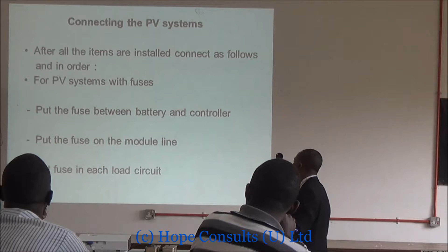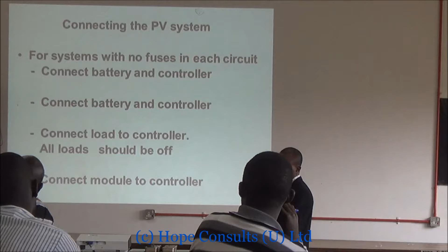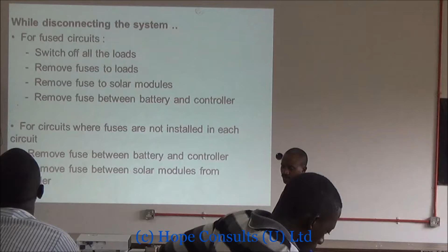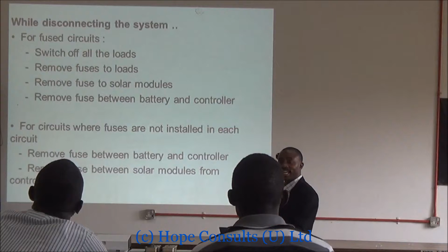For systems with no fuses in each circuit, connect the battery and the charge controller, and then connect the load to the controller. Also, all loads should be off. You connect the module to the controller. At least the charge controller controls the amount of charge coming in, so in case you don't have the fuses, you make sure that the charge controller is helping you in that respect. That is not really a big concern for now.